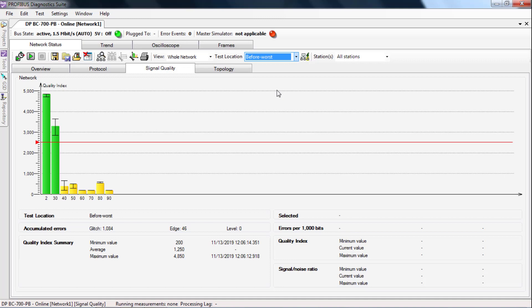In our case, the termination at the beginning is missing. This happens, for example, if the shifter on the bus connector is set to on, but the internal switch did not engage correctly.